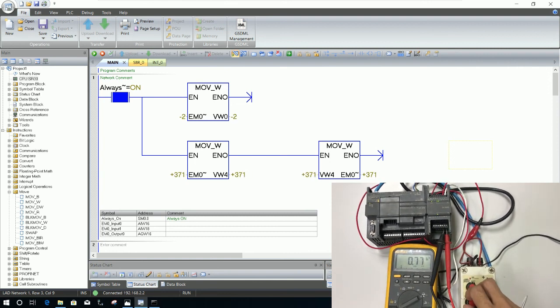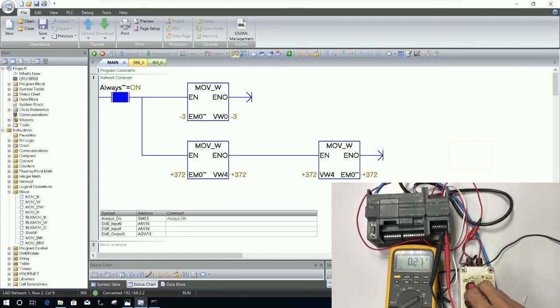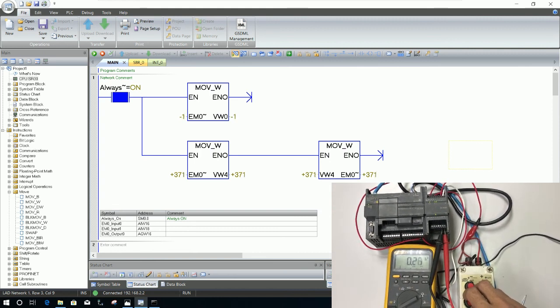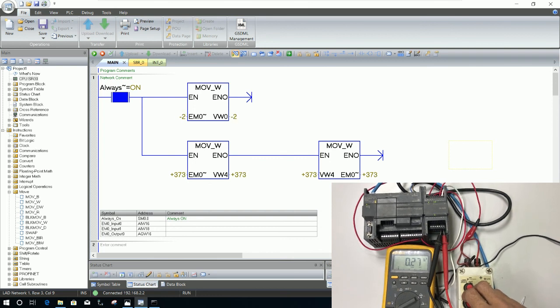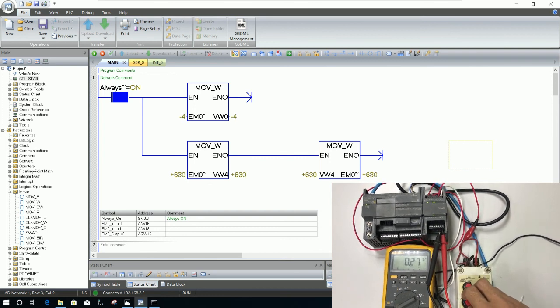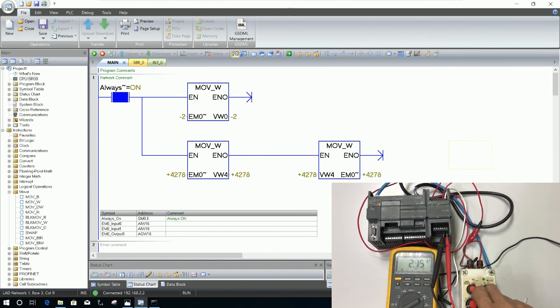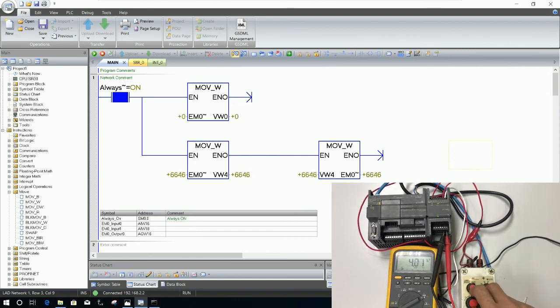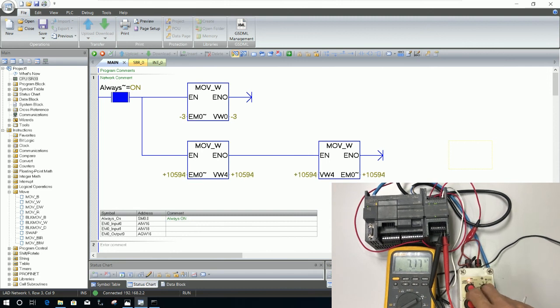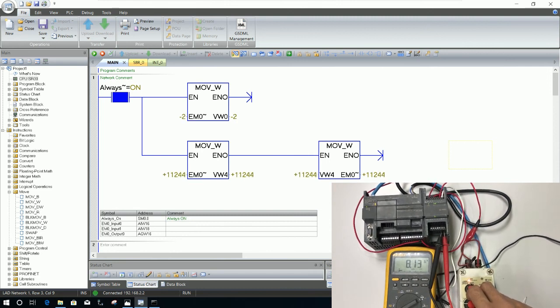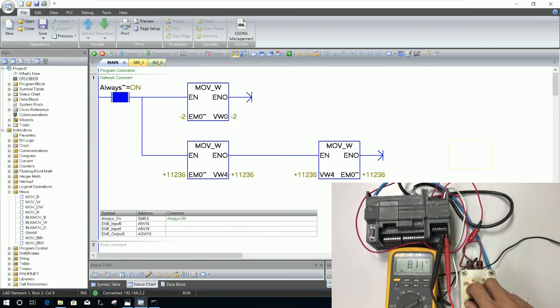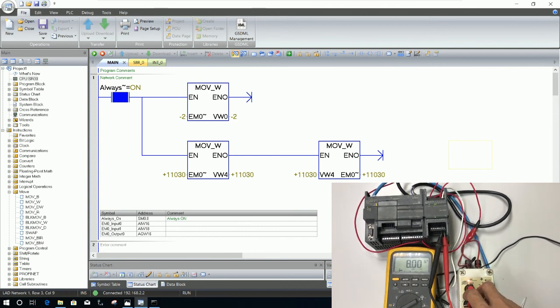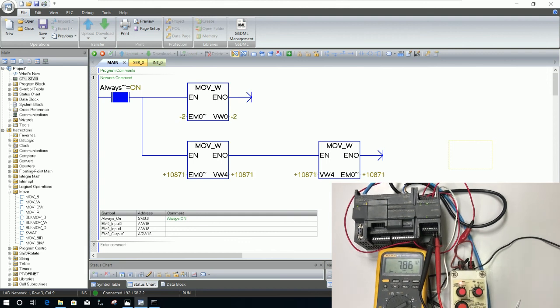Zero, okay, it's half milliamp, a little bit, not zero, zero point something. When I adjust to 16 or 8 milliamp for example, it will generate 8 milliamp or so to our analog output module.